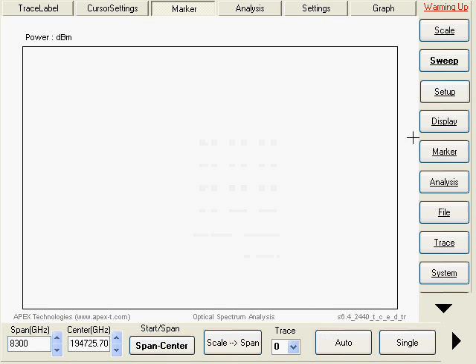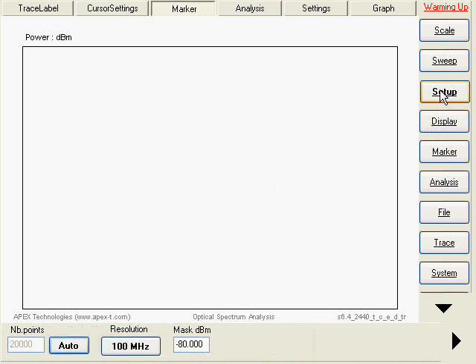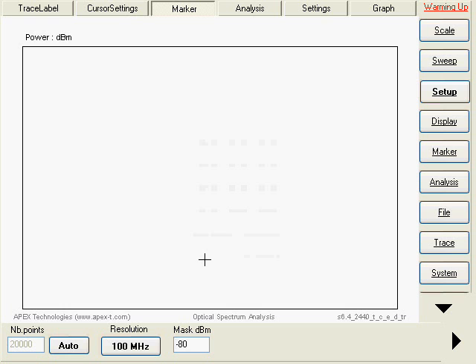Then, we will set the mask level. Due to the fact that the spectrum analyzer has a very low noise, we will set it at minus 80 dBm.